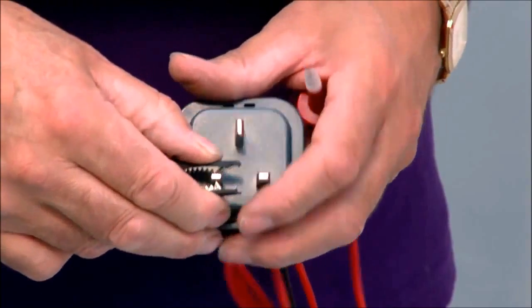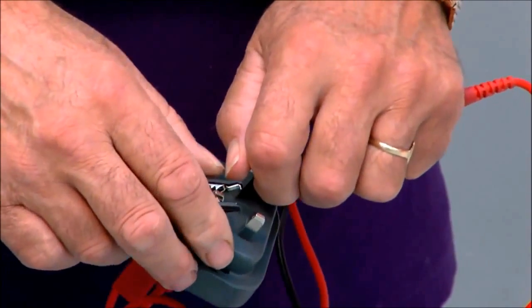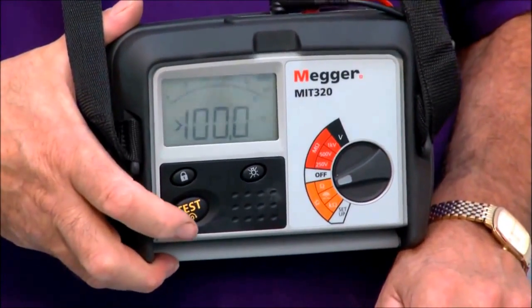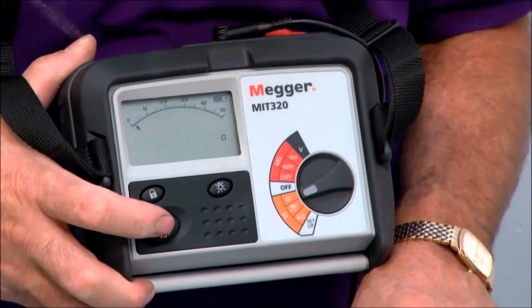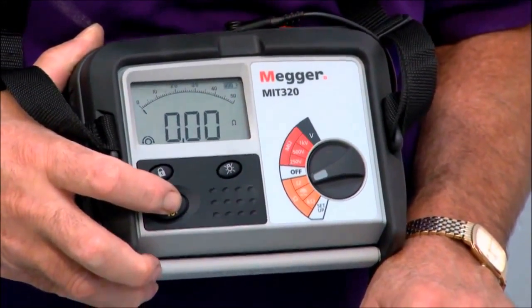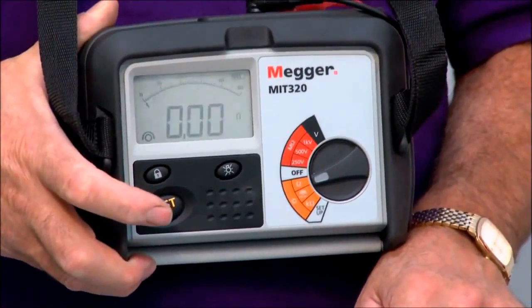I've isolated this circuit. This is the furthest point on the circuit, which is the one I want to take the R1 and R2 reading from. What I need to do now is zero the instrument to take into account the resistance of the instrument leads and also the piece of equipment I'm using for carrying out the test. So quite a simple process. I'll just turn my instrument to ohms, take a reading, push the button, and when that little symbol comes up on the bottom left-hand corner, that's showing me that this is now zeroed.